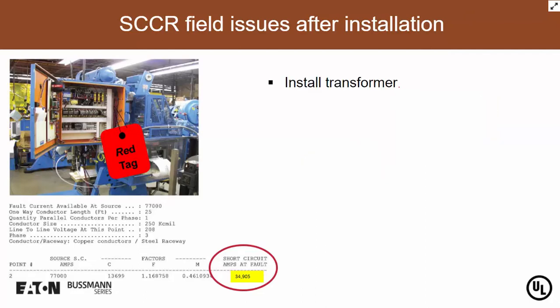All right, so what can we do? Well, we can install a transformer in front of it, hopefully drop the fault current to below 10,000 amps, and then we cover the SCCR of this machine. So we can do that if we wanted to. That's expensive. Or we can add conductors. So basically, we disconnect the conductor out of this machine, run it around the building a couple times, and then bring it back into the machine. And because of the resistance in the conductors, basically we've dropped the fault current to below 10,000 amps to cover this machine. That is not necessarily feasible, but it's one of our options that we could possibly do.